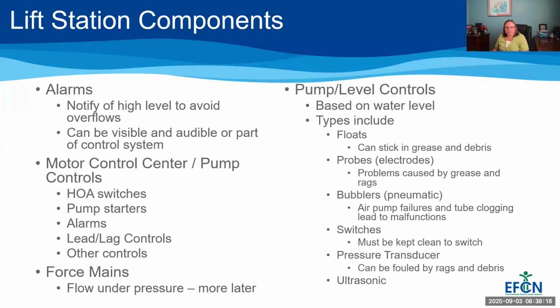So we have probes or electrode controllers, and they utilize electrode probes or a lead. It's an open circuit, like an open electrical circuit, until the water level rises. And when both electrodes get wet, it sends a current, which causes the control circuit on the pump to turn on. And then when the water level drops, the probe is exposed, the circuit's open, and the pump shuts off. And again, this type of level control can have problems caused by grease and caused by rags.